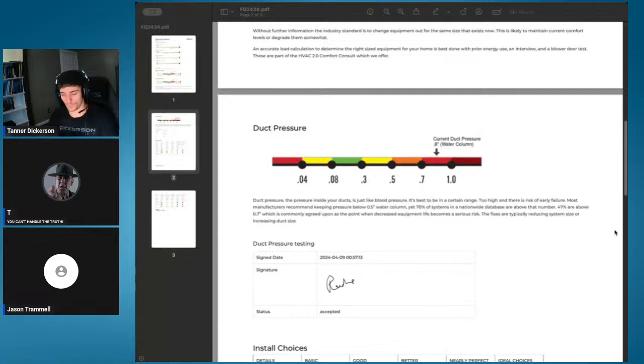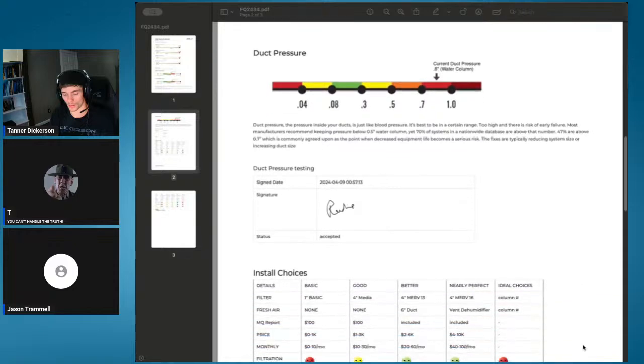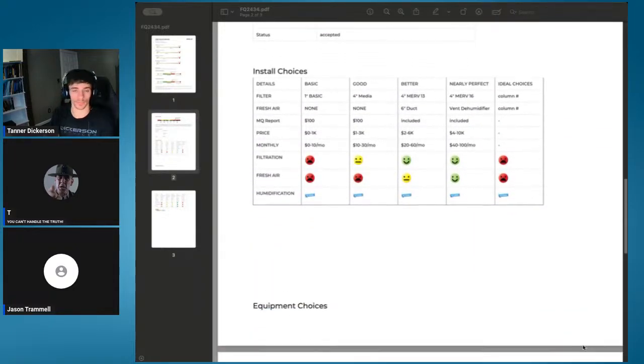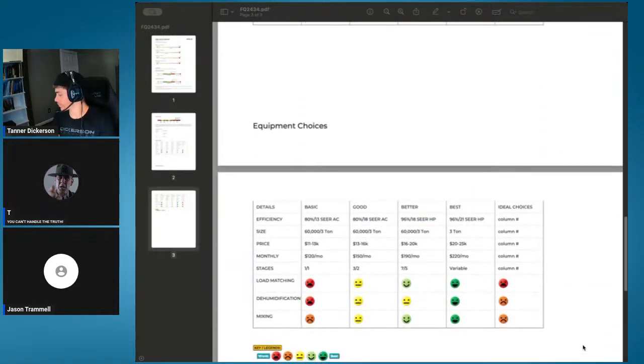That's on you. If you have a way of proving that, it's way easier to fix than an oversized system with static pressure through the roof. You're going to have to replace ductwork or replace equipment if you get the equipment wrong at sale, whereas if you get the install wrong, that's much easier to fix, through a process that documents how decisions were made, who took the risk, who took responsibility, and that you educated the homeowner about their decisions and opportunities.